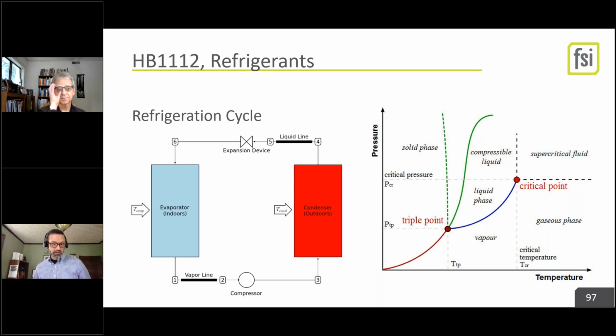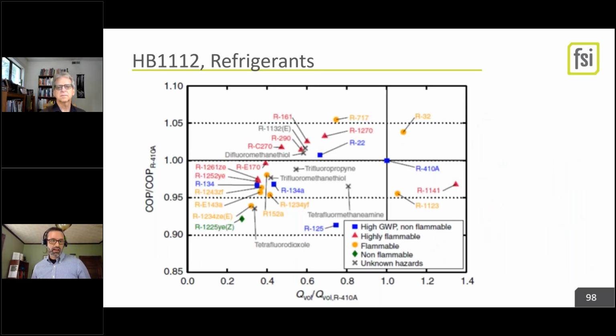Our ideal refrigerant, R410A, was pretty good. This is all weighted to R410A, so it's ratioed out. But R410A was really good, except that it has this high global warming potential. R32 lives in that greater than R410A, better COP, better performance, and better heat carrying capacity. And it's also slightly flammable. So our next version isn't currently code allowed in big enough systems. So that's looking at the VRFs of the world again with the big refrigerant volumes. You could hypothetically, with a gigantic leak, maybe build up to the lower flammability limit. We can talk about that if you want in questions.